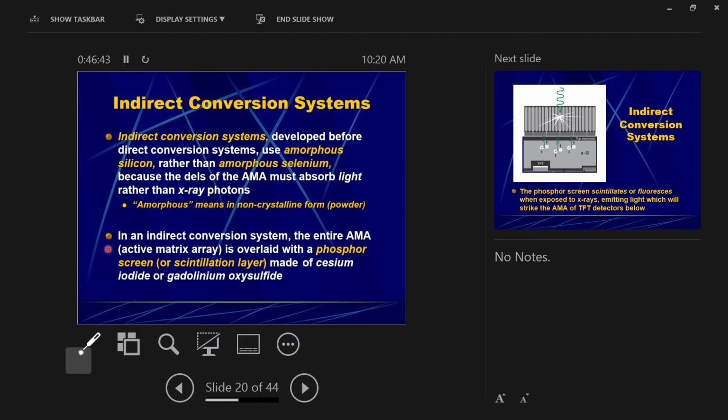What you need to know about scintillator screens is that they convert one type of electromagnetic energy into another. If you want to just get the basics, scintillation is converting one type of electromagnetic radiation into another, for example, X-rays being converted into visible light. You could also refer to them as a phosphor screen, because phosphorescence is something giving off light when it is struck by another type of light. For example, when X-rays strike this phosphor screen, the phosphor screen absorbs the X-rays and emits visible light.